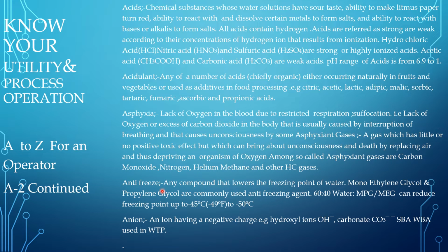We can see another important terminology: antifreeze. Any compound that lowers the freezing point of water. Monoethylene glycol and monopropylene glycol are commonly used antifreezing agents. Normally 60% water and 40% MPG or MEG are used. It can reduce the freezing point down to minus 45 to minus 50 degrees centigrade.